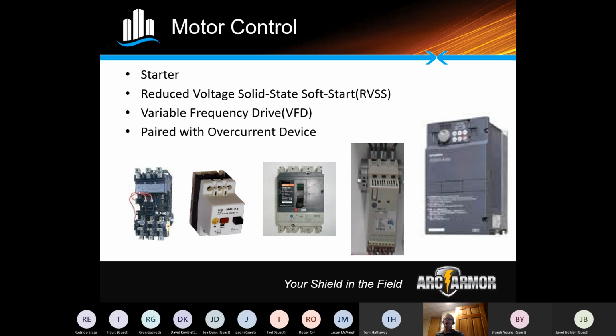The reason for that is if you were to keep the solid state starters engaged all the time, that's a huge heat generator. And so now you would run into a lot of issues with trying to offload heat, just like you do with a drive. So sometimes these can be more conducive in panels where you don't want to put the ventilation that may be required for a variable frequency drive, especially if they're outdoors.